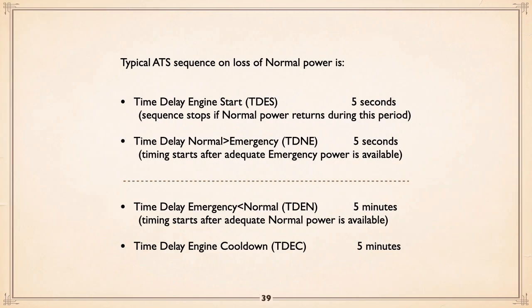Now, how the normal sequence goes is like this. You can set the timers to what you want. This is what I use because it's easy to remember: you hold out your hand and you've got a thumb, but you call it 5 fingers, okay? So first off, the transfer switch has a time delay engine start. It counts out 5 seconds. In other words, if the line power comes back within 5 seconds, it was a momentary blip. Don't worry about it. The power comes back on and everybody's happy. You've probably got your equipment programmed so that after a power loss, it will automatically delay before it starts things back up. But in terms of the transfer switch, it doesn't do anything if the power restores itself within 5 seconds. If it doesn't, it will start the engine.